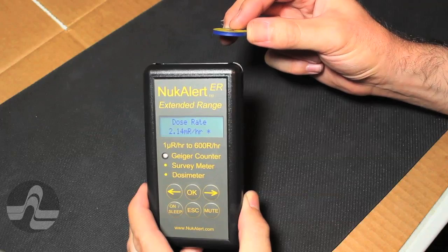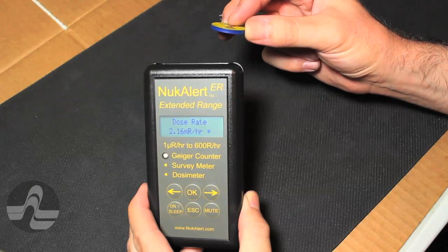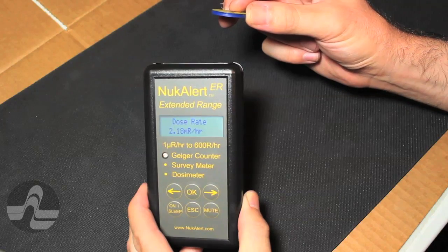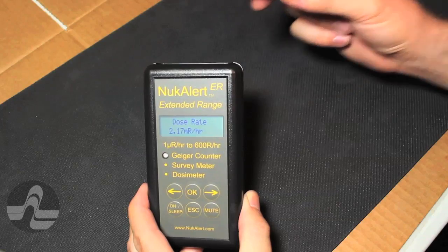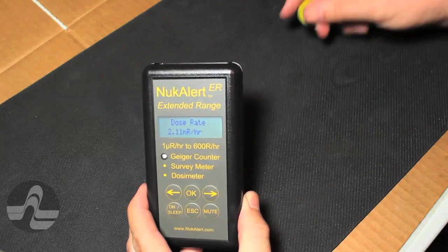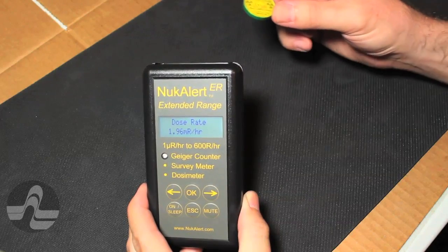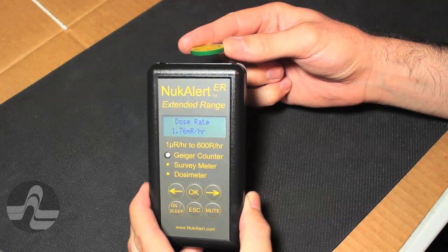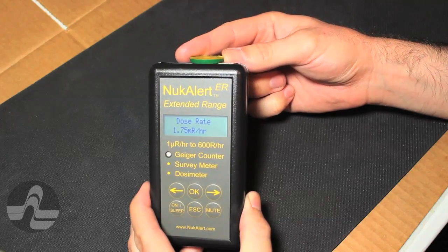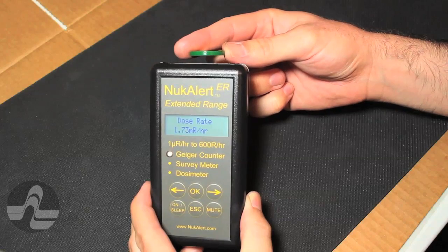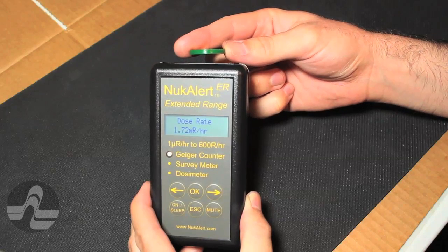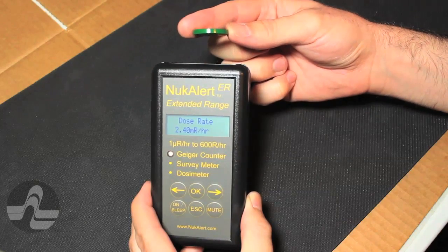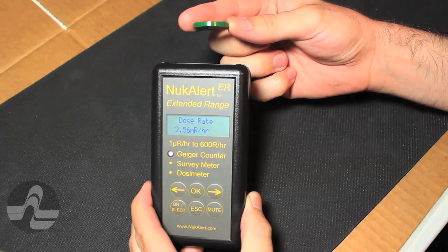The asterisk on the home screen indicates that the averaging window time has not fully elapsed. The averaging window is set to 15 seconds for quick response to test sources. The averaging time can be set as high as 30 minutes. Dose rate is presented in three significant figure engineering notation and seamlessly transitions from micro-R per hour to hundreds of R per hour without user intervention.